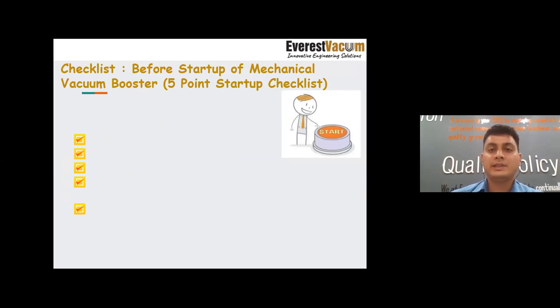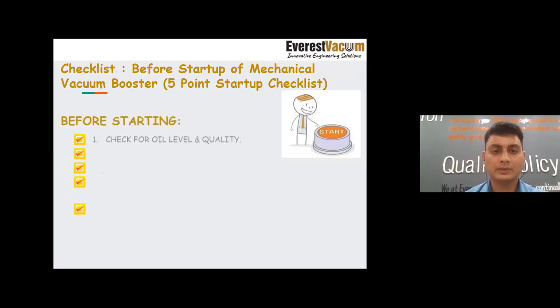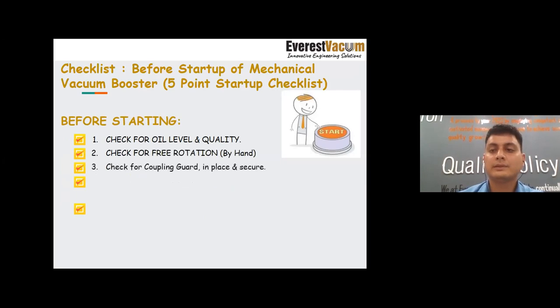Now this is the checklist before startup of the mechanical vacuum booster. This is a 5-point start checklist. So before starting, we need to check the oil level and its quality. Check for free rotation by hand. Check the coupling guard. Is it in place and secure?